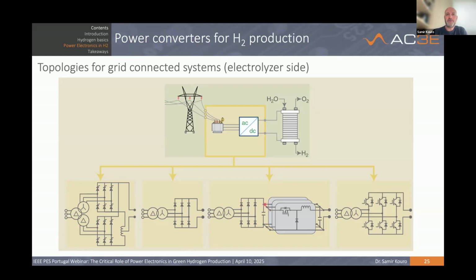And then there are other solutions based on diode bridge rectifiers, followed by power electronics that can perform any form of power factor correction. These usually have open-end windings over here in order to be able to do the power factor correction. And then you have fully controlled rectifiers that are capable of having very good power quality at the input, like the voltage source converter. Usually those are connected in parallel as well, so in interleaved operation, in order to increase the current going into the electrolyzer. But basically rectifiers, AC-DC rectifiers.